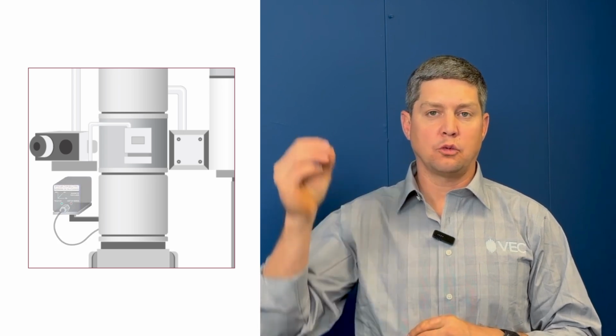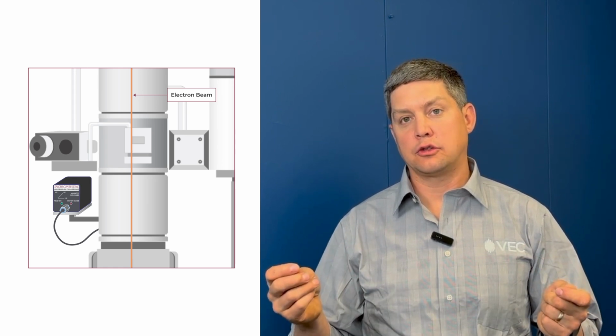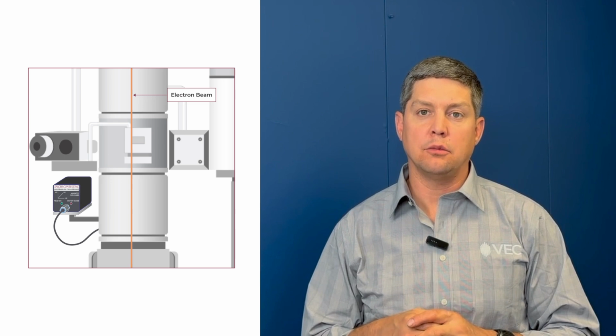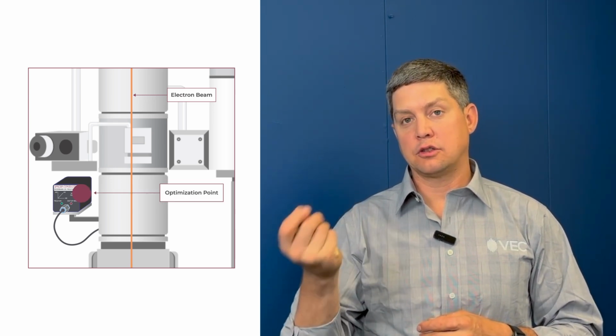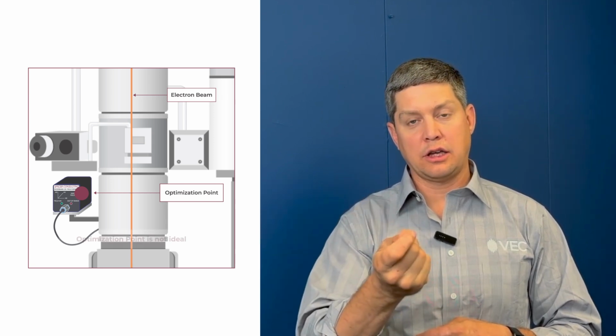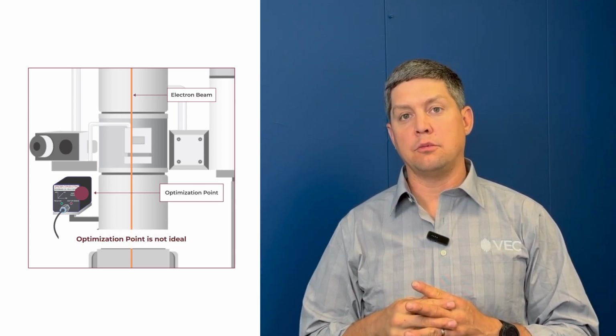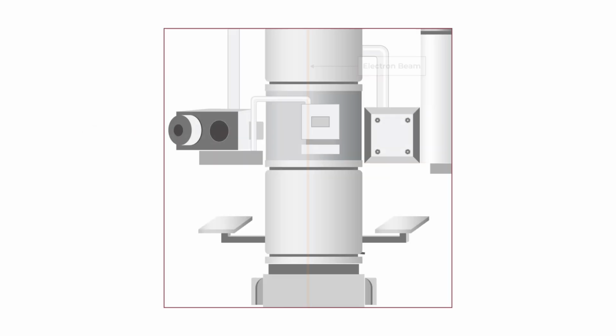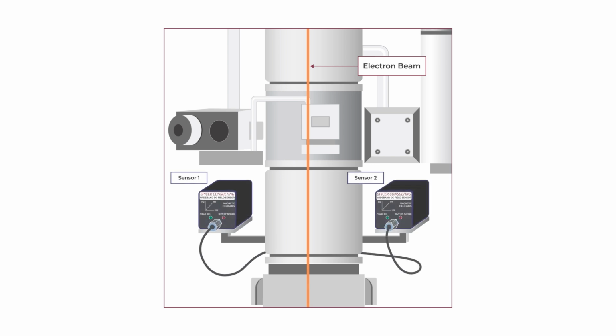So with VEC, in addition to being able to use a dual cancellation system to optimize two systems, one for the top and one for the bottom of the microscope, we use what we call a virtual sensor, using two individual sensors to create an optimization point inside the electron beam column. Because the field cancellation system is optimized for the sensor location, if you have one sensor and it is not inside the electron beam column, the optimization point for the system isn't really where it matters the most, because it's not at the electron beam. But if you use two sensors, one on either side of the column, and you take a mixing of the signals and create a weighted average in the center of the column, it allows you to create a virtual sensor at the electron beam inside the column of the microscope, where cancellation matters the most.